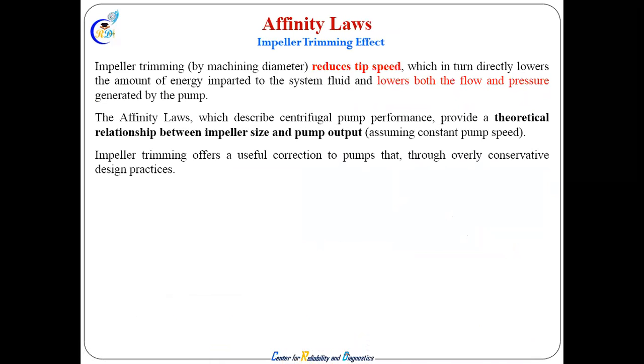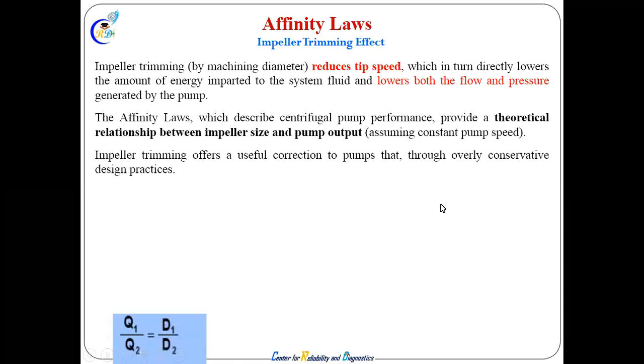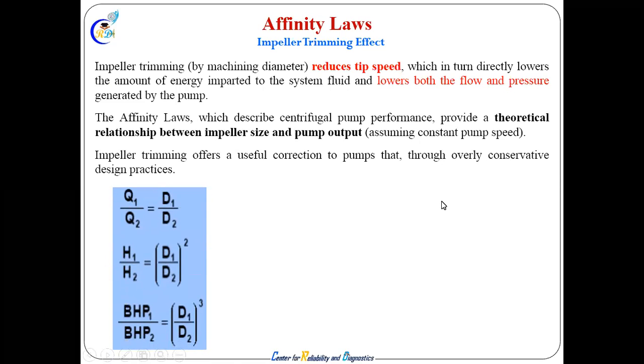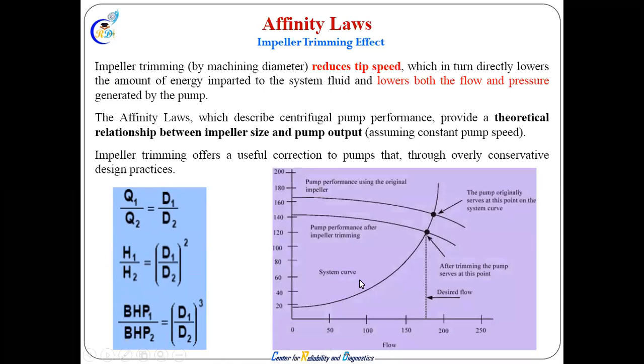You have purchased a 500 mm impeller, and you want to make it some 400 mm within the flow requirement. Then you can do impeller trimming, which is very important. That is frequently done, and I have cases here that I will show you. By changing the impeller, you get a new curve from the beginning, but you can see you are encountering the same system curve, not an issue. And after trimming, you get the reduced flow which you want, the desired flow.